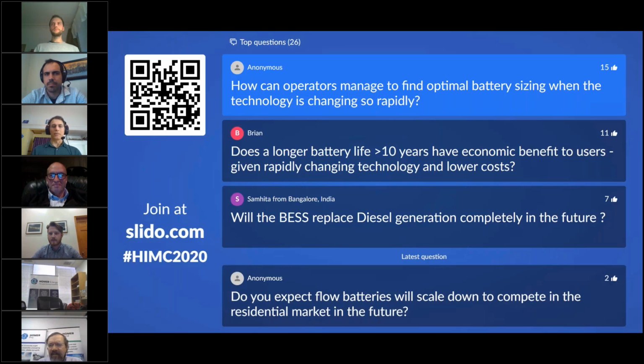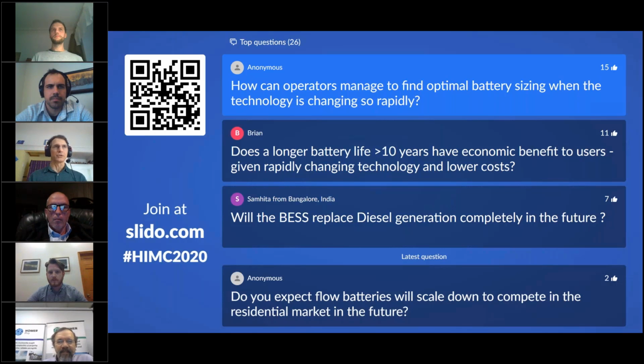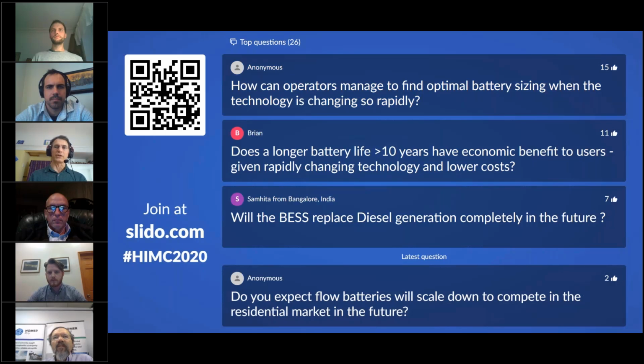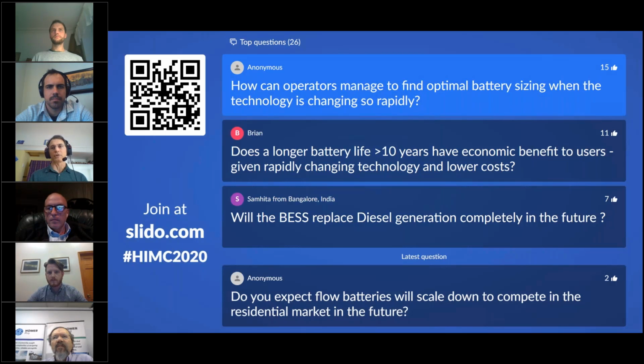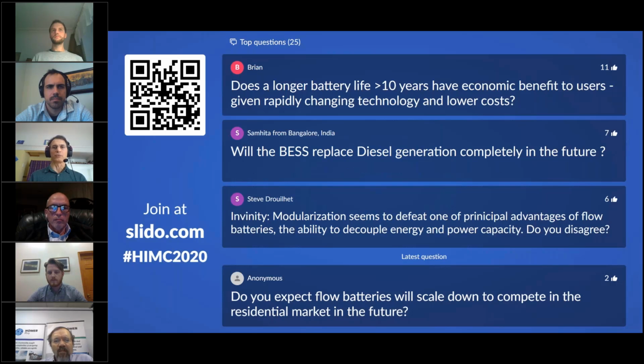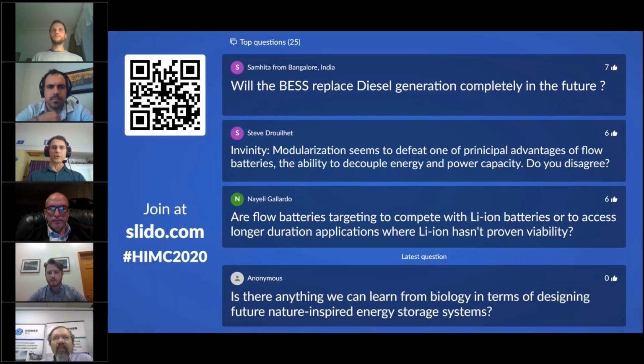I'd just add one thing: if you're going to take that strategy, remember that the factors making you want to replace a battery for performance reasons, or because it's approaching only 80% of original rated capacity, those same factors also increase your risk of fire events. That's the other motivation for performing a replacement. So if you're following the squeak-by strategy, you need to make sure, as you really should with any energy storage system, that you've got a well thought out fire detection and suppression system.